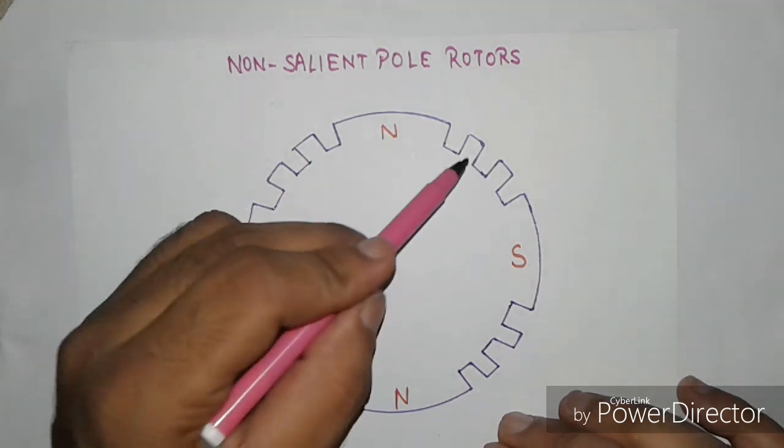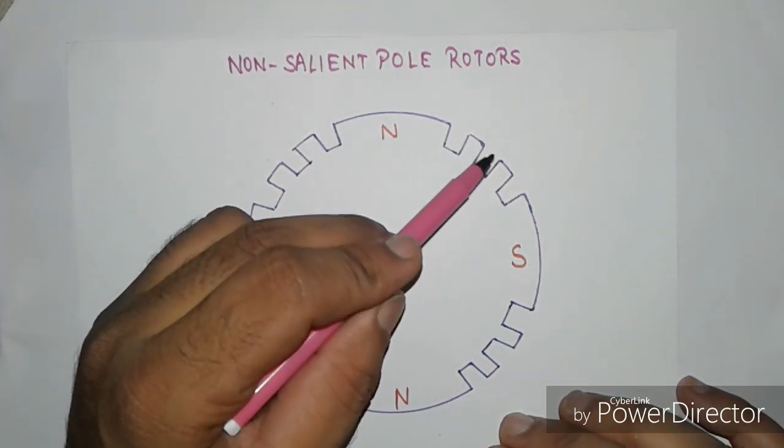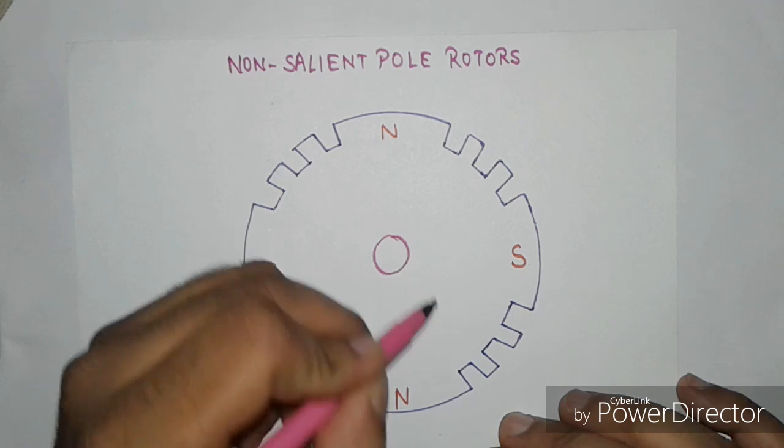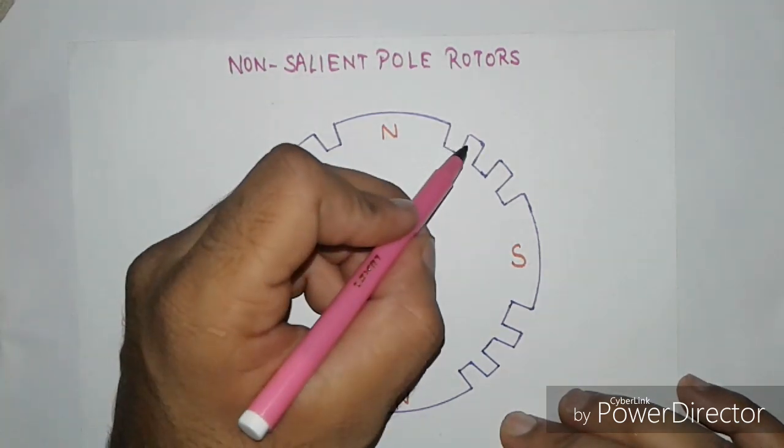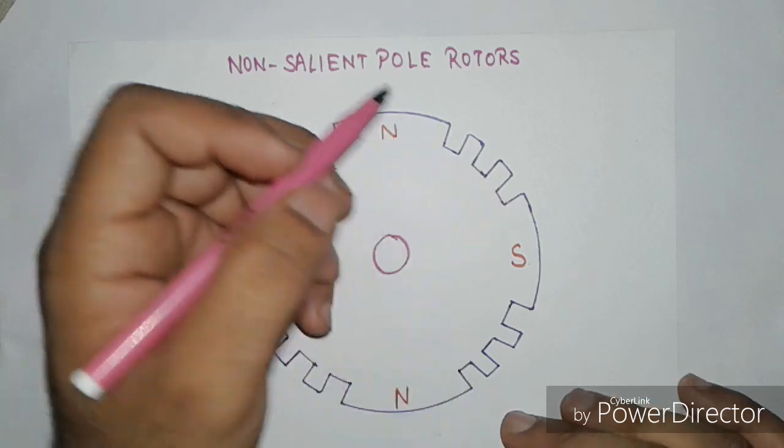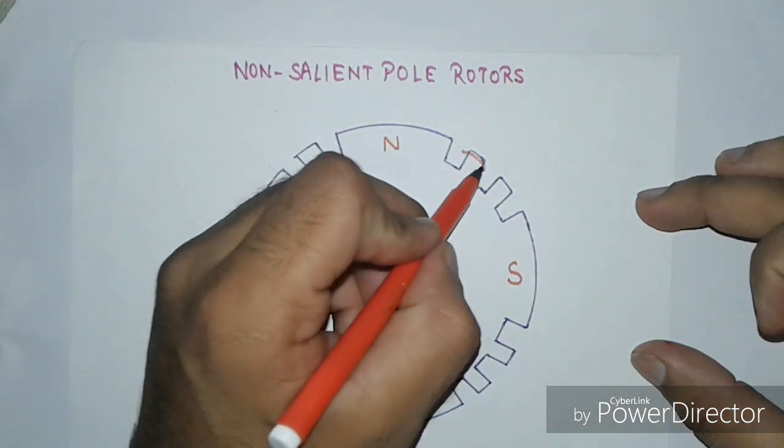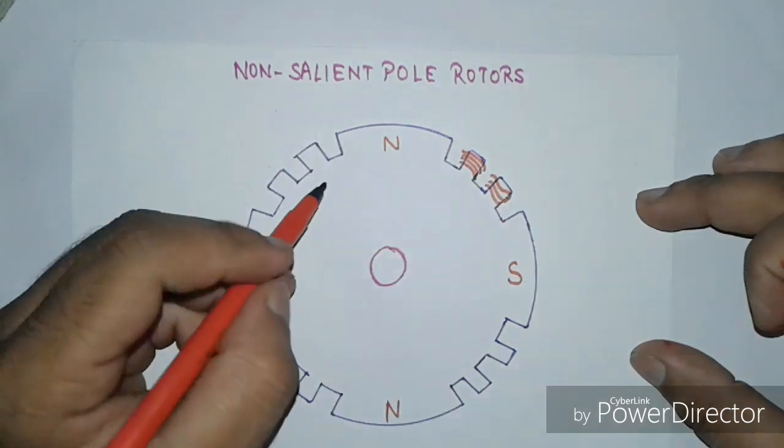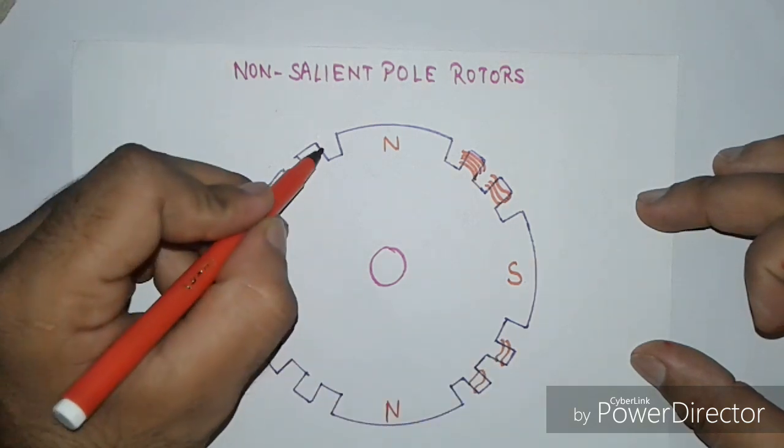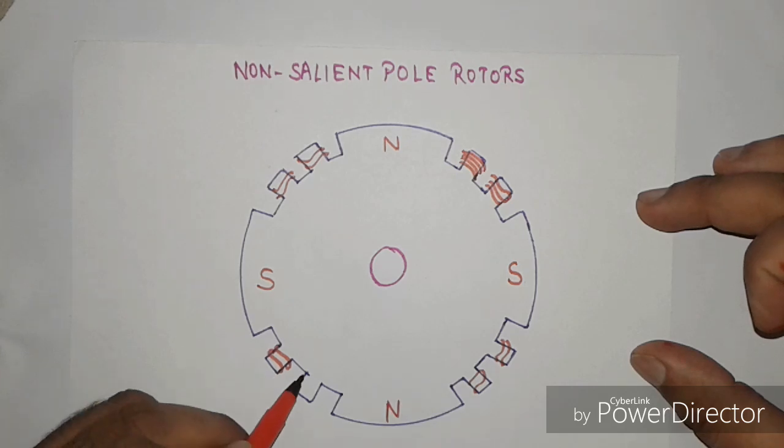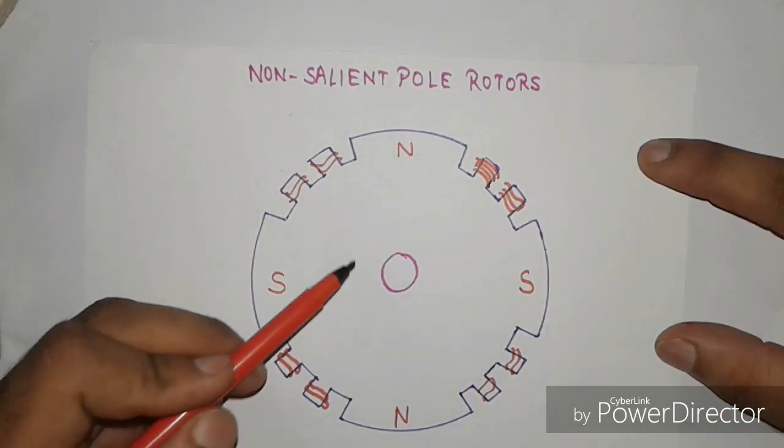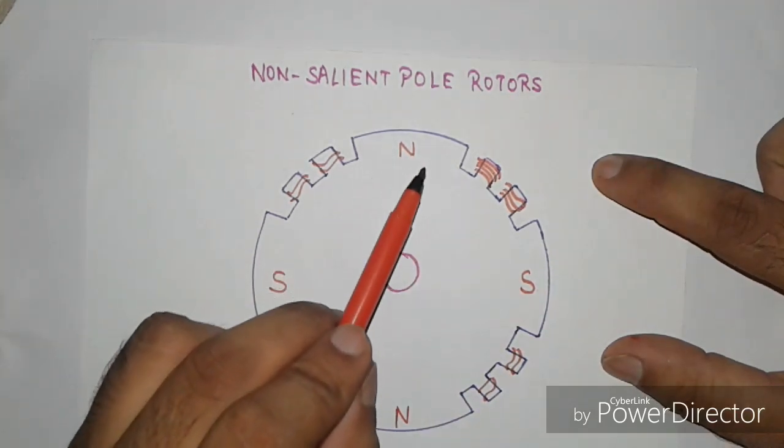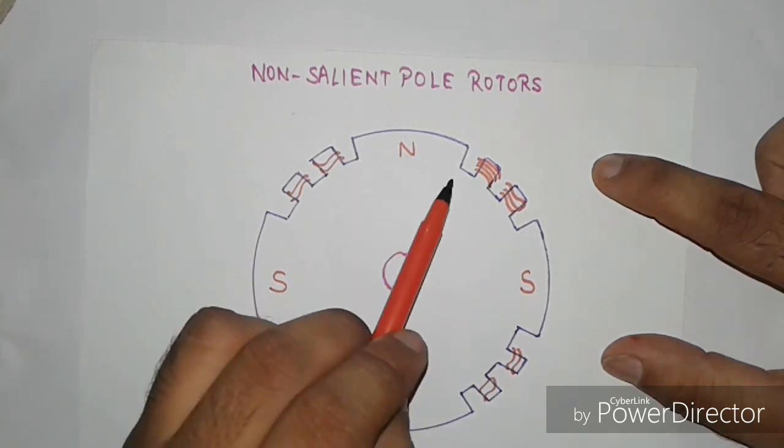In about two-thirds of the rotor periphery, slots are cut at regular intervals parallel to the shaft. The DC field winding is done in these slots. This winding is of distributed type. The unslotted portion of the rotor forms two or four pole faces.